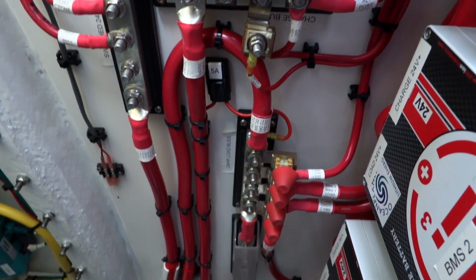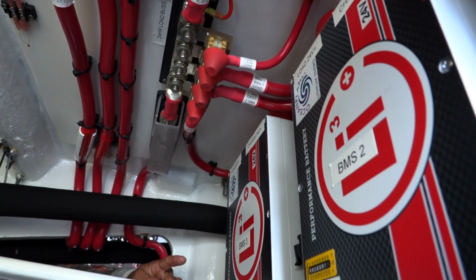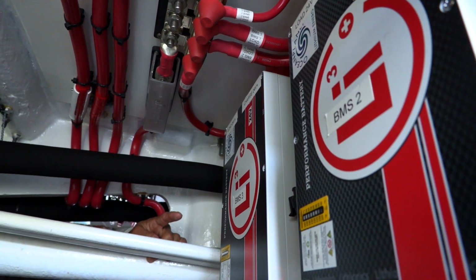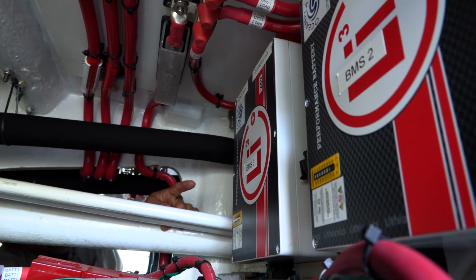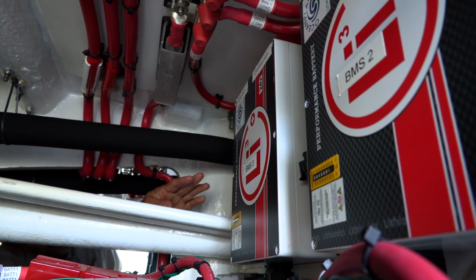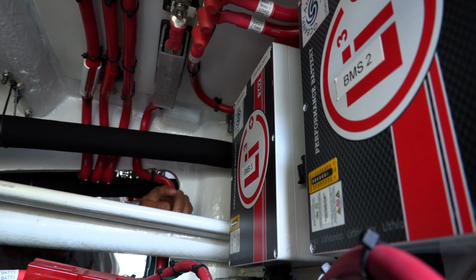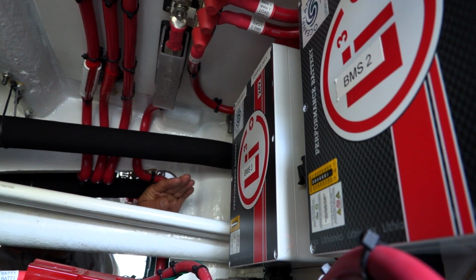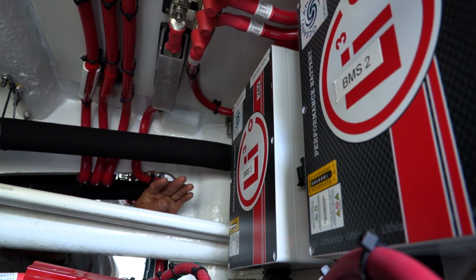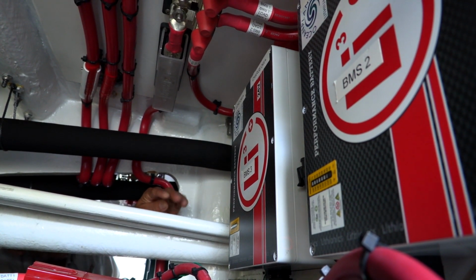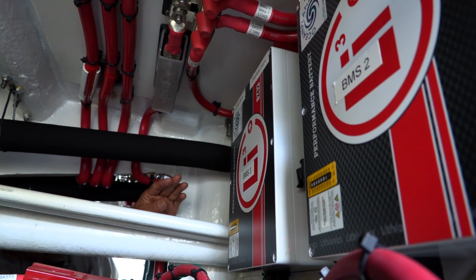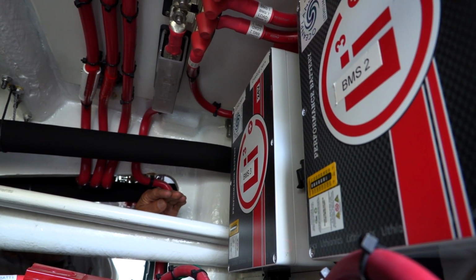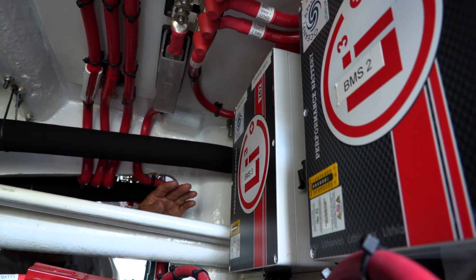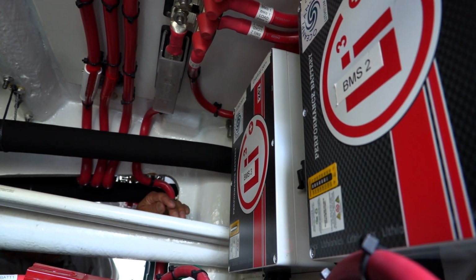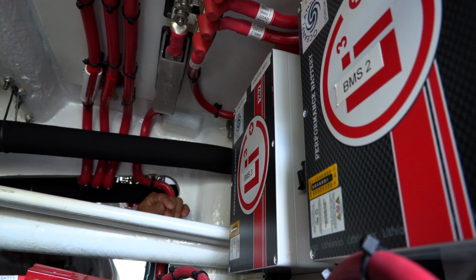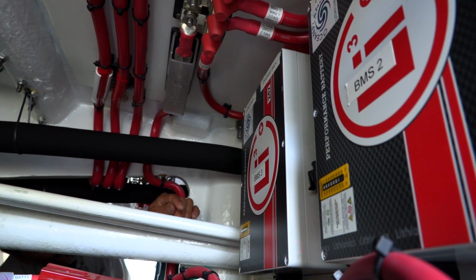Here you can see the 3 BMS modules, which means Battery Management System — control boxes, one for each battery, that control the charge and discharge of the system. All of the contactors that can cut off the battery and protect it are inside these boxes. As complicated as this stuff may look, this is much less complicated than earlier lithium systems where you had to install all the contactors manually. Here they're all inside the box — it bolts up much simpler and much faster to install than the old way of doing it.